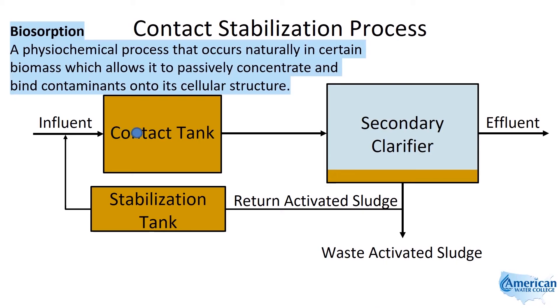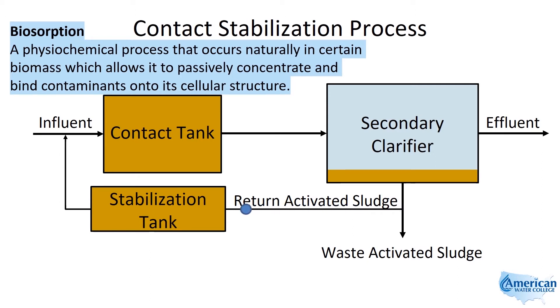In the contact stabilization process, the influent water enters the contact tank where it remains for about 30 minutes to an hour, which is a shorter duration than for a conventional system. The microbes are expected to quickly undergo biosorption, and in that process they take up the BOD that's in the wastewater.